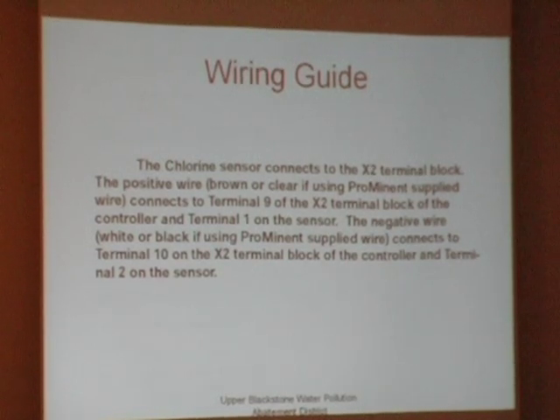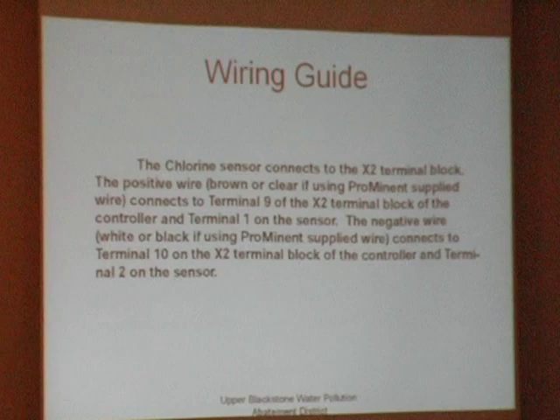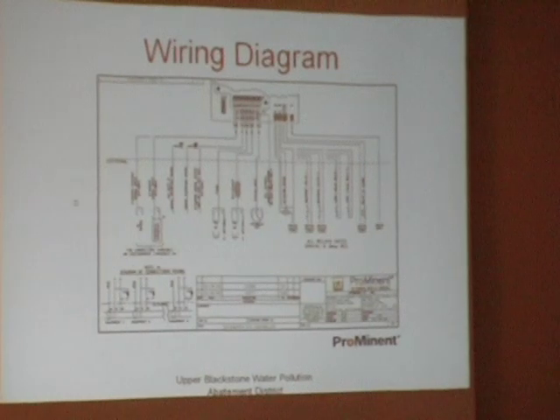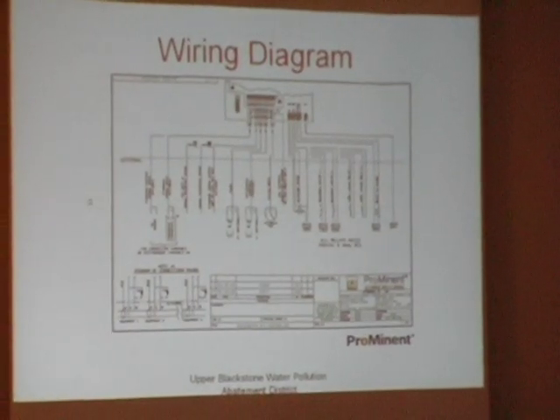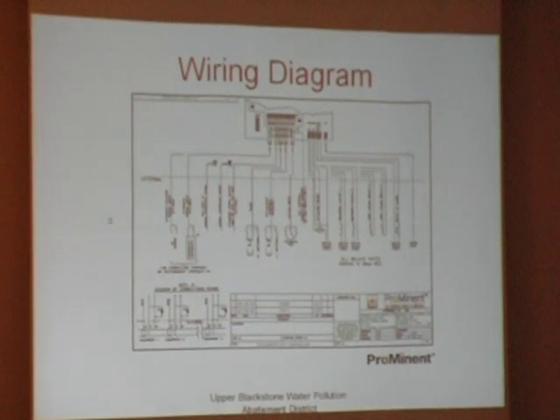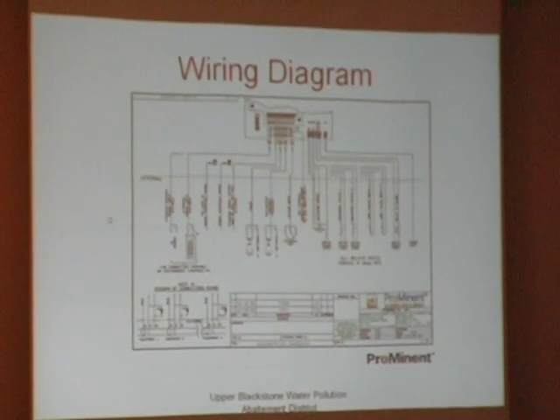In this manual is a wiring guide, and basically two wires that go to two terminals on the end of the sensor, and then it connects into two terminals on this box. And this little wiring guide, again, which you have in there, tells you exactly which terminals things are to reside on. Real simple. If you really wanted to get into this thing, well, there's a full wiring diagram if you wanted that too. And again, this instrument has the ability of alarming on high or low and taking other inputs or actually sending out control signals. But again, all you're using this for is monitoring with the 4 to 20 going to your SCADA system.